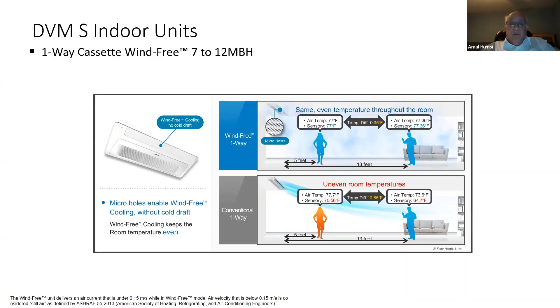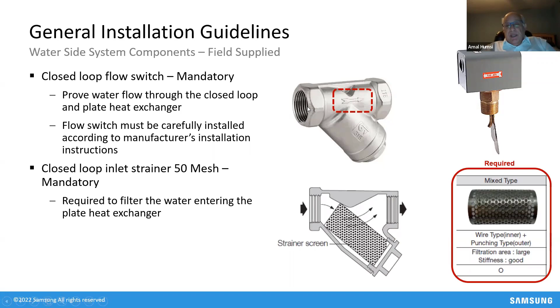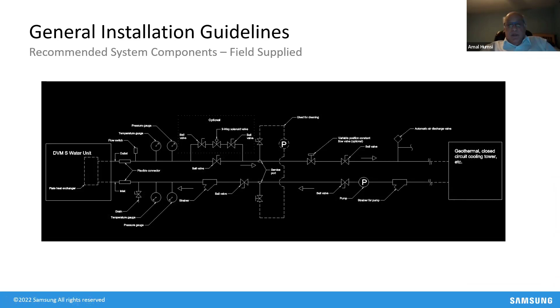In terms of guidelines, Samsung requires only two things. The first thing that Samsung requires is a flow switch. So if there's no water flowing through the system, you are going to get an error message. And the other thing that Samsung requires is a 50 mesh strainer. Those are the only two. And then you can build the system, whatever you like, ball valves, cleaning ports, whatever you want. But the strainer and the flow switch, those are the two things that Samsung requires.